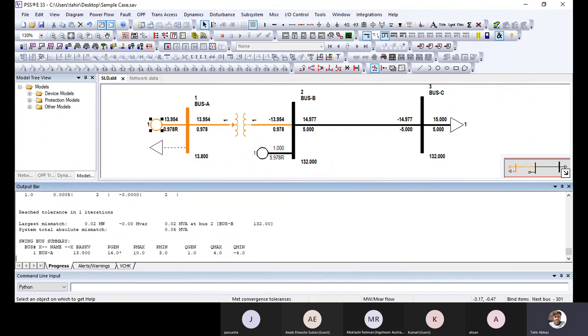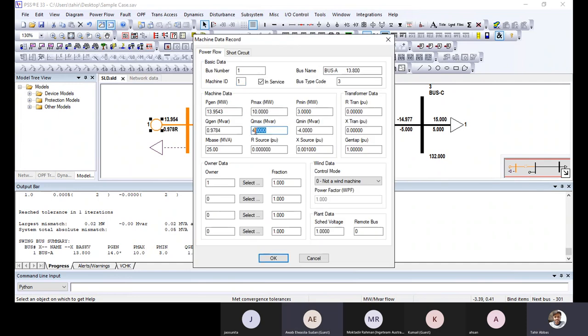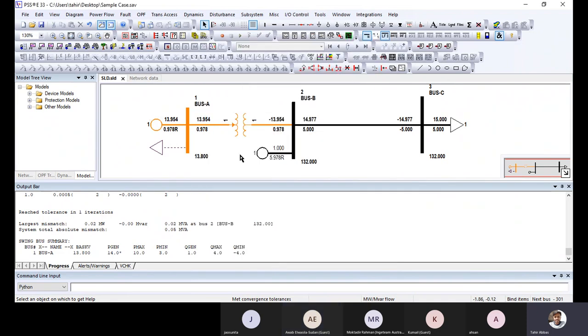Okay, anyone else? I want to ask about the R near the machine. Does it indicate reactive power? Yes, basically this is the range of reactive power. Here you can see that I have added the Q max and Q min, so it means that the generator is supplying within the range. Basically, this is the curve.